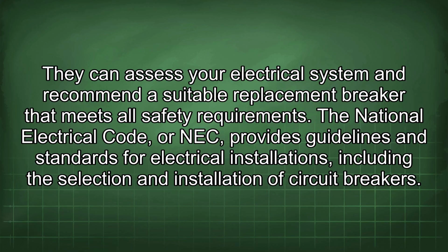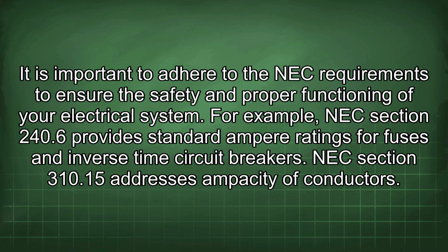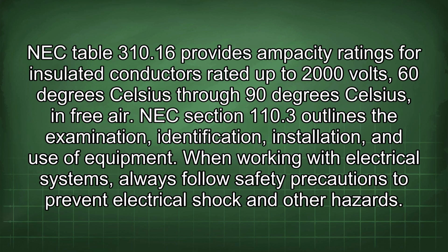The National Electrical Code, or NEC, provides guidelines and standards for electrical installations, including the selection and installation of circuit breakers. It is important to adhere to the NEC requirements to ensure the safety and proper functioning of your electrical system. For example, NEC Section 240.6 provides standard ampere ratings for fuses and inverse time circuit breakers. NEC Section 310.15 addresses ampacity of conductors. NEC Table 310.16 provides ampacity ratings for insulated conductors rated up to 2000 volts, 60 degrees Celsius through 90 degrees Celsius, in free air. NEC Section 110.3 outlines the examination, identification, installation, and use of equipment.